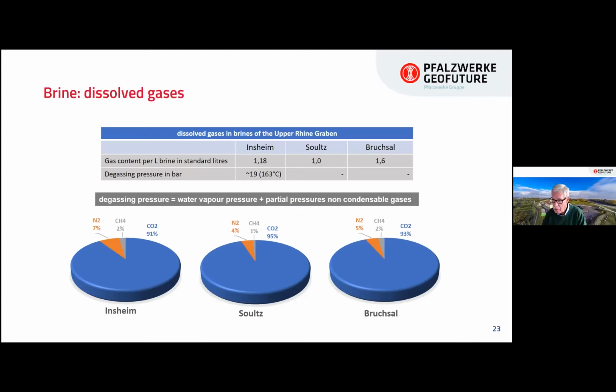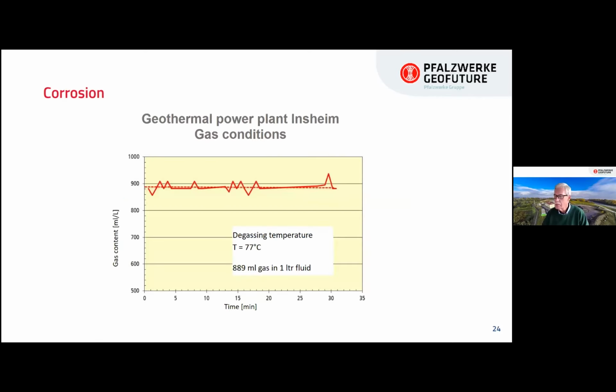But on the other hand, of course, we have to operate the whole brine system above the degassing pressure, which is between 19 and 20 bars, different from site to site, to keep the carbon dioxide within the brine.